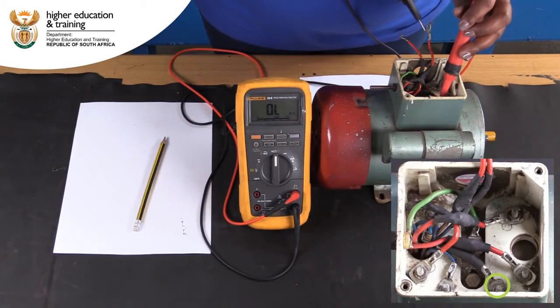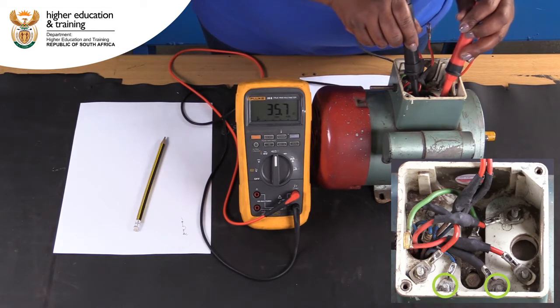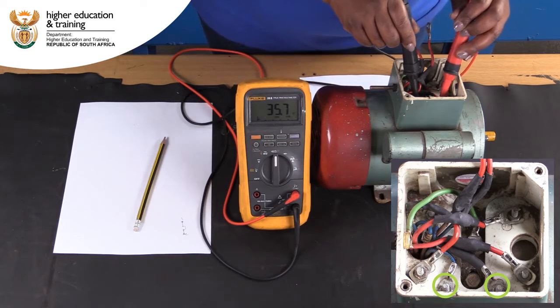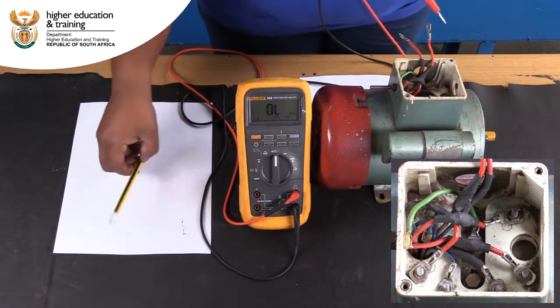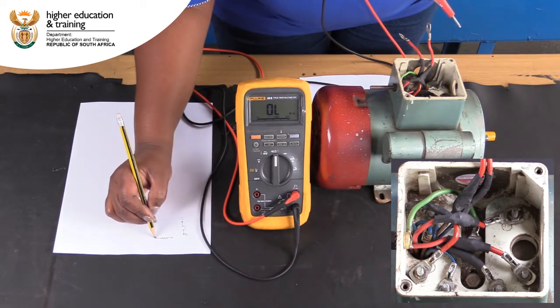Between posts 3 and 4, we get a reading of 35.7 ohms. This is quite a large reading, so probably indicates the start winding. Make a note of this result on your own terminal block diagram.